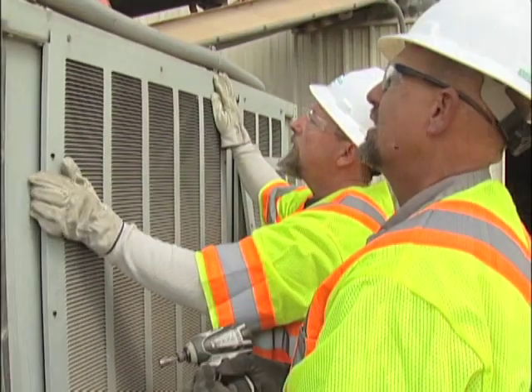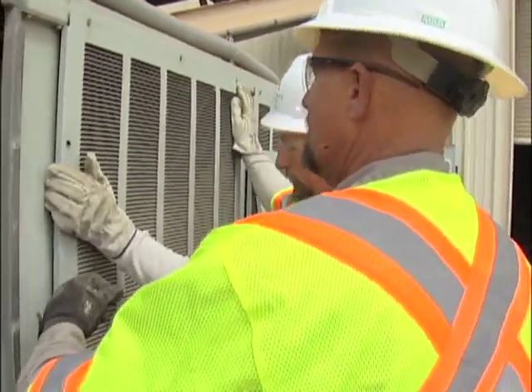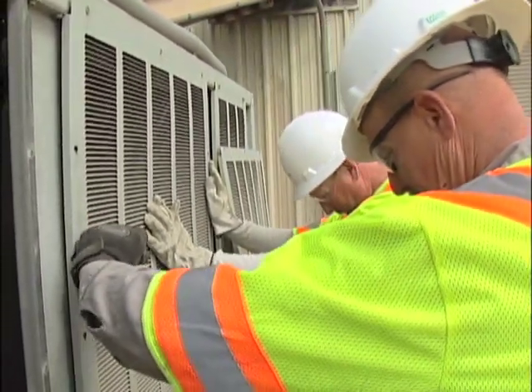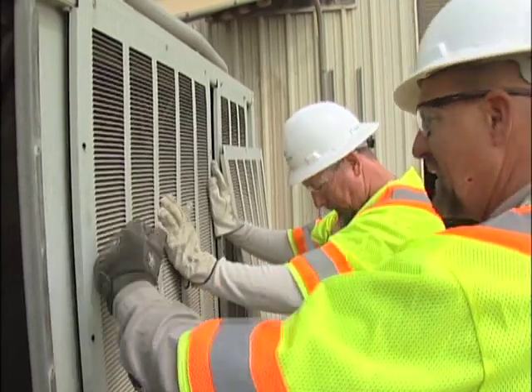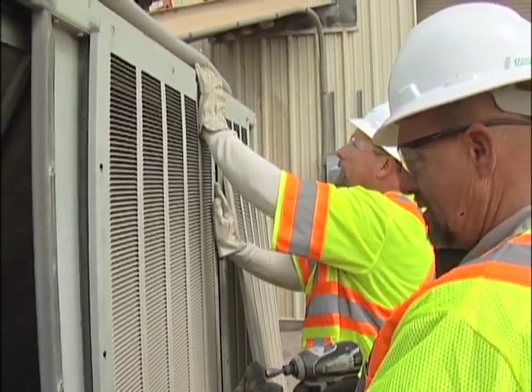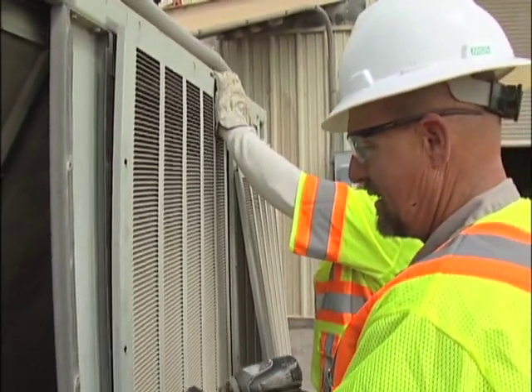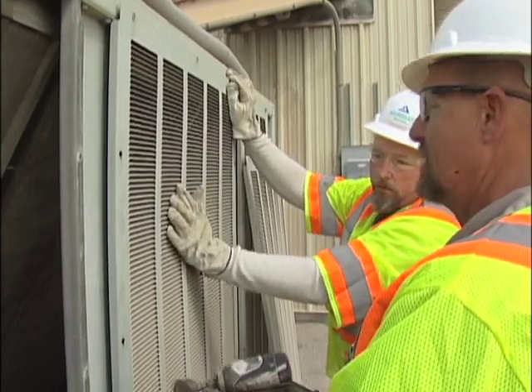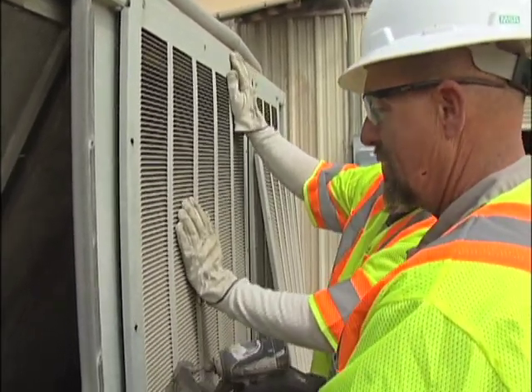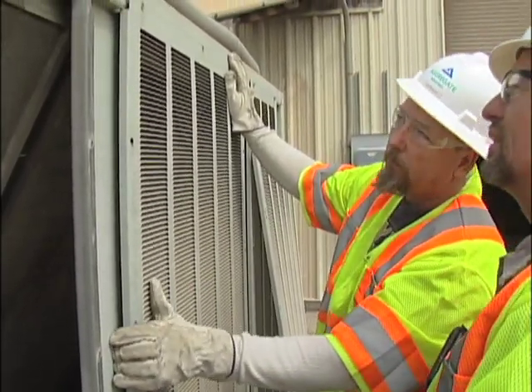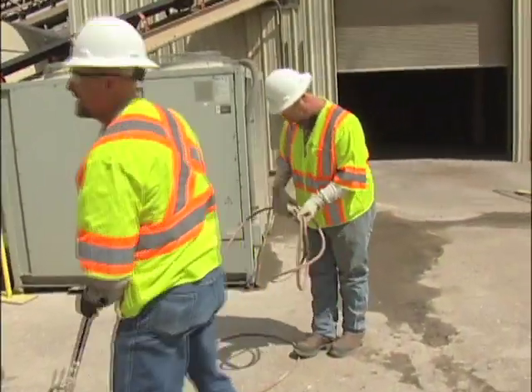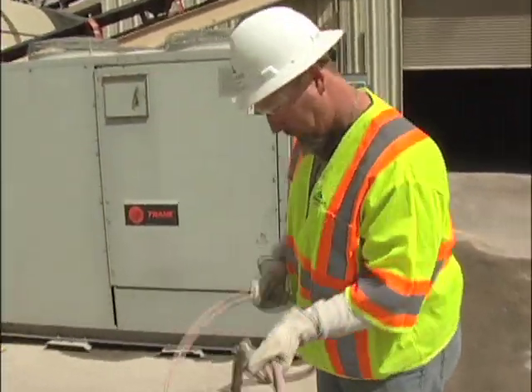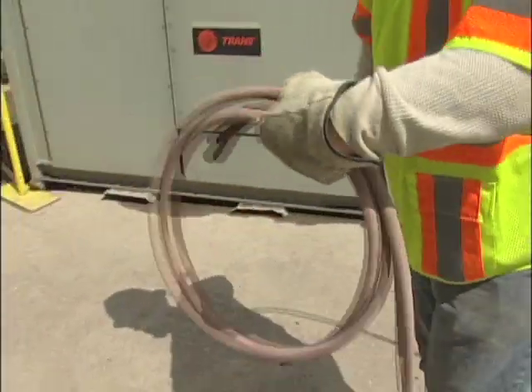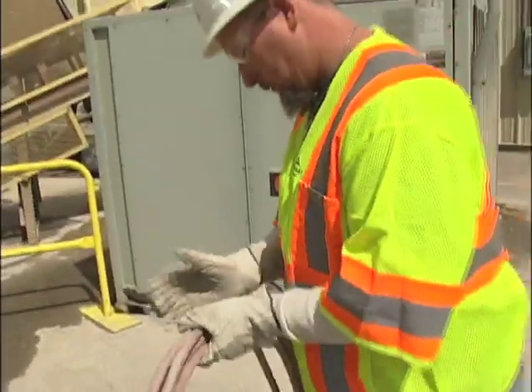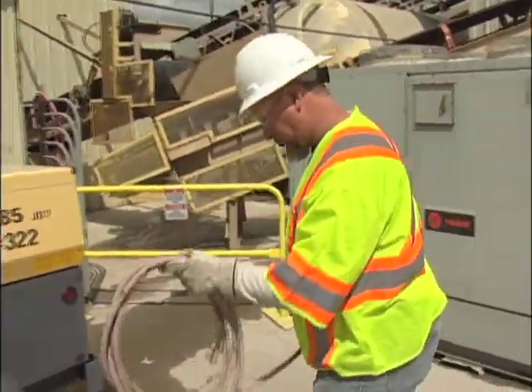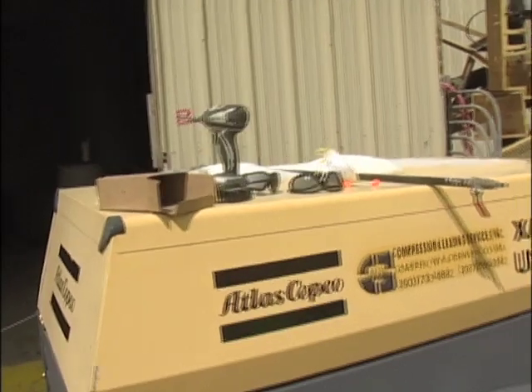Number 9. For reversal of a lockout tagout tryout procedure and removal of lockout tagout devices, follow these steps. A. All machine or equipment guards must be reinstalled, secured, and in place. B. All tools must be removed. C. Ensure the machine components are operational and intact. Remove any and all non-essential items.